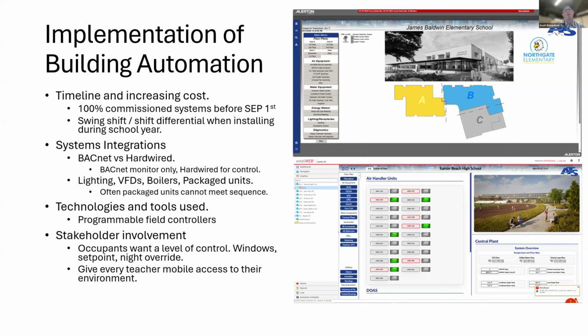suppliers do provide fully capable sequenced controllers, and they'll sell you, all you've got to do is land a communication card or a communication network on this, and you're good to go. But what we found is the manufacturer's sequences don't always work that great. And if you're not familiar with the controls, if it's not the controls that you are using on your site as a whole, then you can't adjust your sequence, or you can't get a local company to help you adjust the sequence. So what we found is we don't want factory controls. Just give us the hardwired inputs to start the fan, adjust the fire rate or whatever you have. So that's true with VFDs, boilers, and other packaged units.